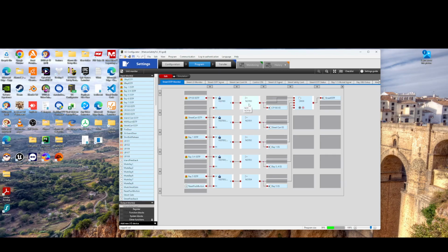The next thing that we have in line is a not block. What this is doing is, if this has been reset and this is true, then this is going to become false. Okay, so as long as your e-stop is good, this will stay false. That's the way it works for each one of these and most of the rest of the code throughout.